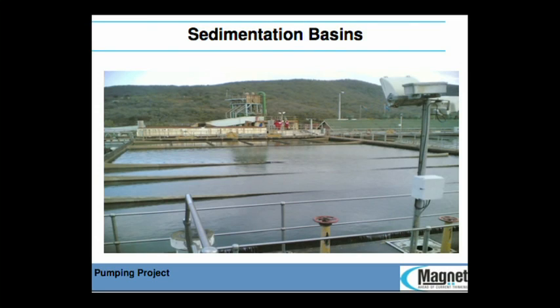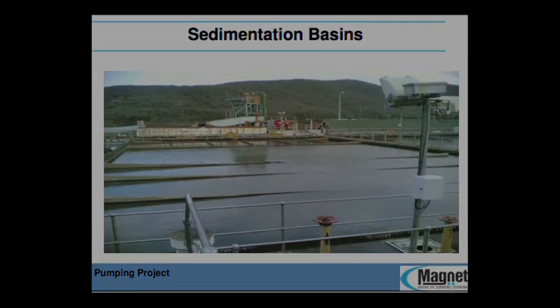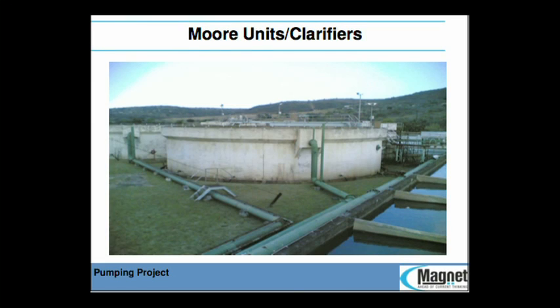Here are the sedimentation basins. They've got the highest throughput of all the sedimentation processes there. That's at plant level. There are 2 of those. These are what they call the Moore units or clarifiers. What historically happened with this plant is they started off with the sedimentation basins, then they needed a bit more capacity, so they added something else, and they added something else, and every time they were adding something, the technology had changed, so we were adding a different piece of equipment.